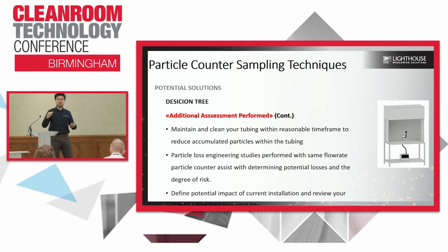If you're not able to do it, you might consider finding the percentage of the loss, plus minus, and lower the alarm and action limits so that, for example, your alarm will not be 100 particles per minute. You may say 70, so that the 30% loss is considered as potential loss with the alarm limit.